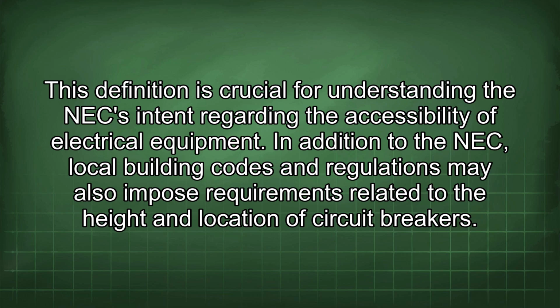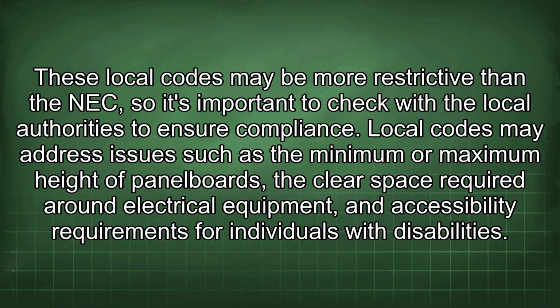In addition to the NEC, local building codes and regulations may also impose requirements related to the height and location of circuit breakers. These local codes may be more restrictive than the NEC, so it's important to check with the local authorities to ensure compliance. Local codes may address issues such as the minimum or maximum height of panelboards, the clear space required around electrical equipment, and accessibility requirements for individuals with disabilities.